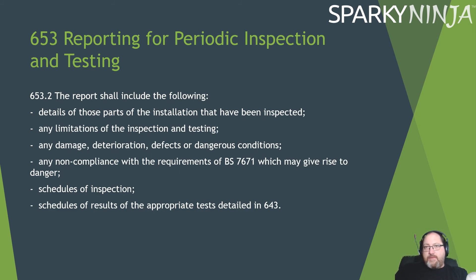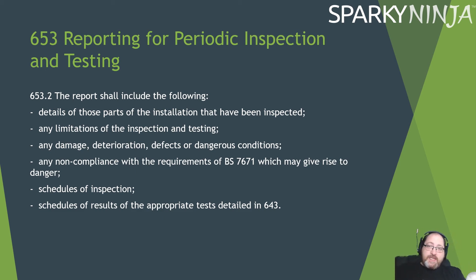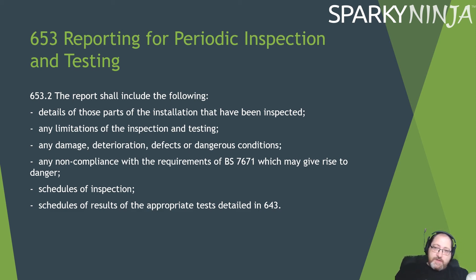Reporting: reports shall also include details of those parts that have been inspected, any limitations, any damage, deterioration, defects or dangerous conditions, non-compliances, schedules of inspections, and schedule of results of the appropriate tests of 643. So that is part of the periodic reporting requirements.